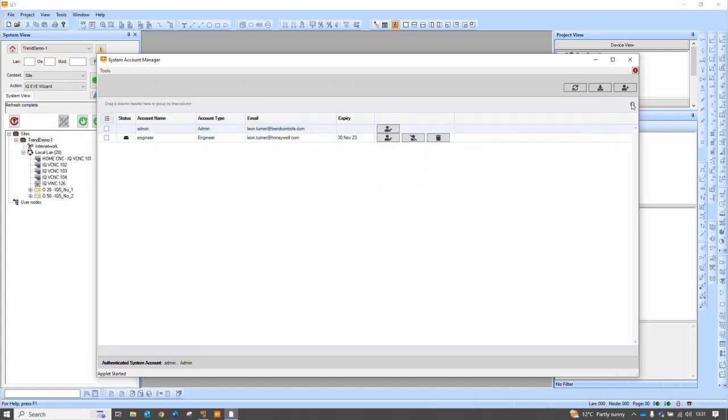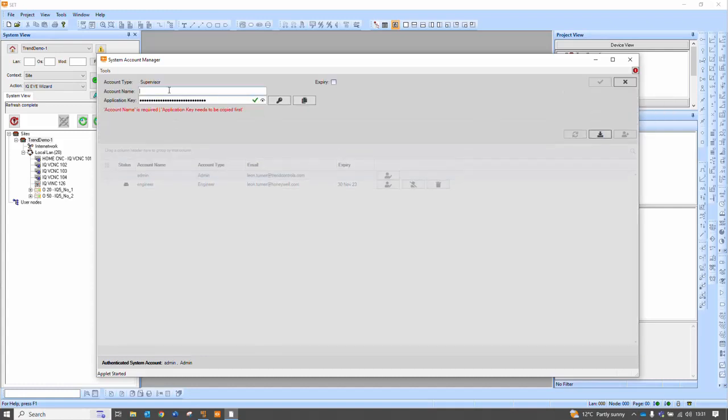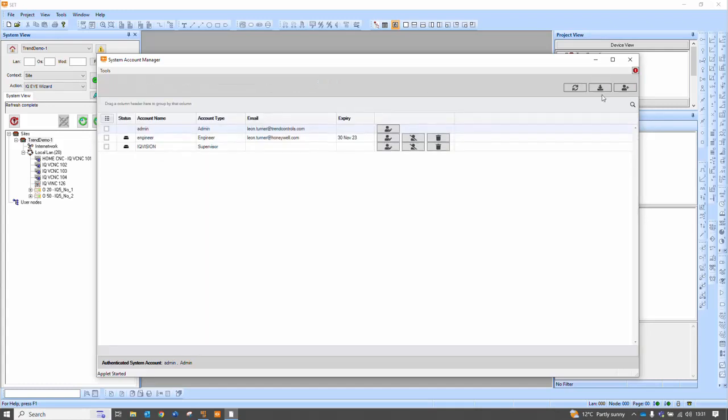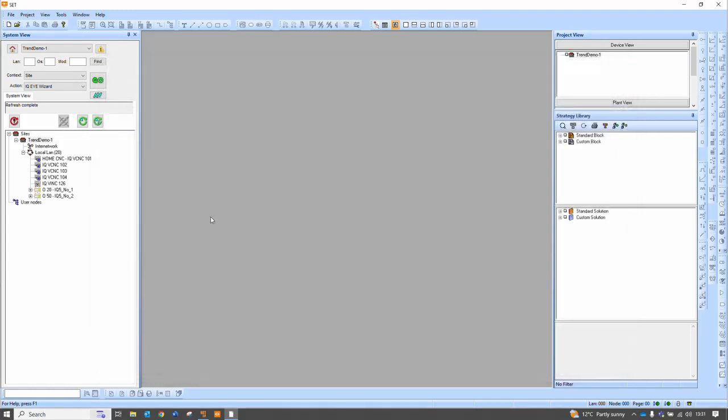And we can go on and add a further one and the supervisor is for IQ Vision, for example. And I copy the application key to the clipboard and then I can use that in IQ Vision to help secure it all. And then it's very simple to just commit that and send it all down. I can have multiples of each one of those type of accounts. And that is it. All of those users have gone down to the controllers and the whole system is synchronized.